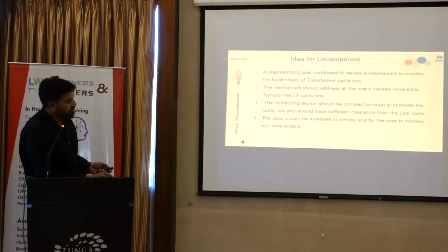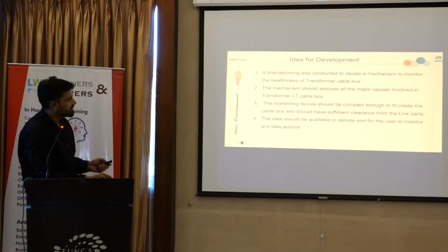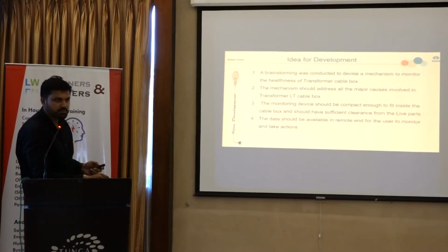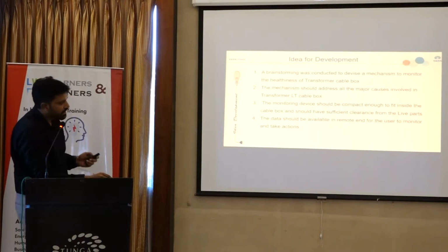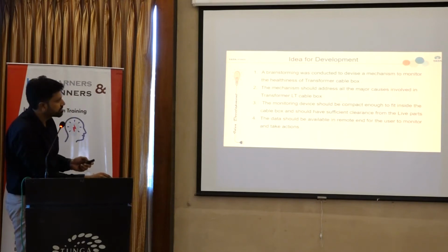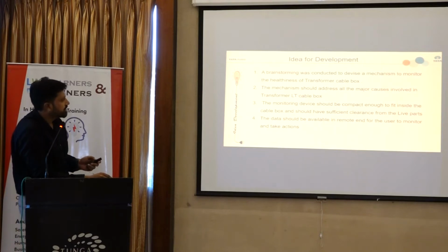The idea for development: we just want to devise a mechanism to monitor this transformer cable box health. So there was a brainstorming session which was conducted to devise a mechanism. The mechanism should also address all the major causes involved in the transformer LT cable box. The monitoring device should be compact enough to fit inside the transformer cable box and should have sufficient clearance from the live parts inside the cable box. And the data should be available at the remote end for the user to monitor and take actions.